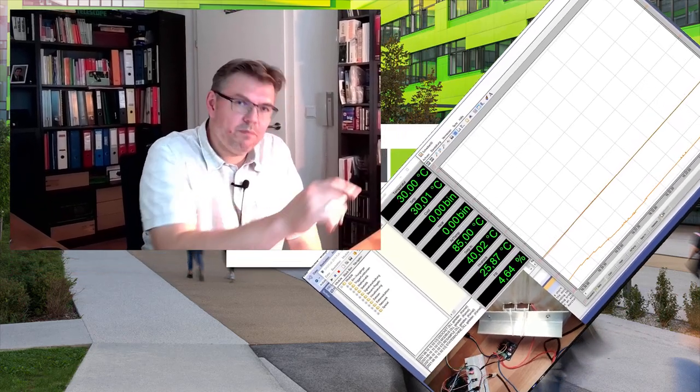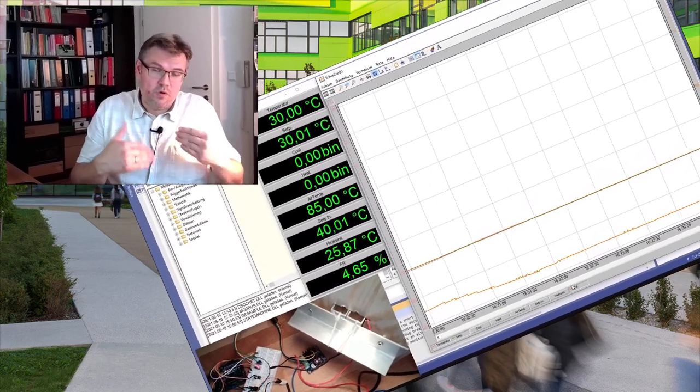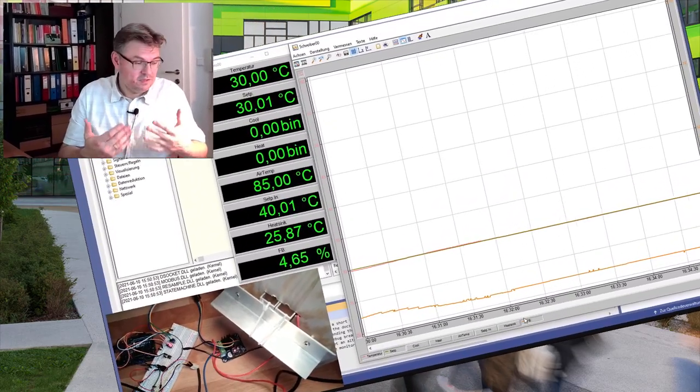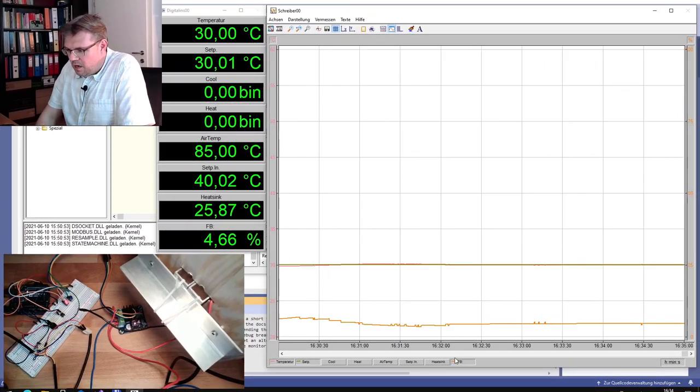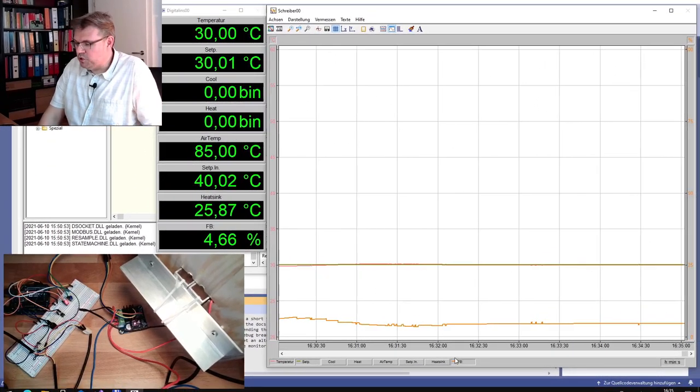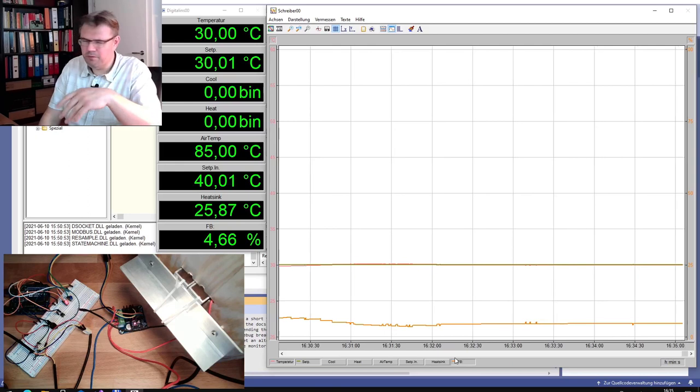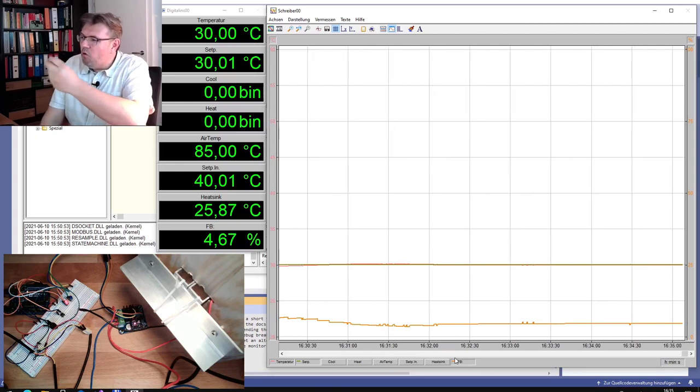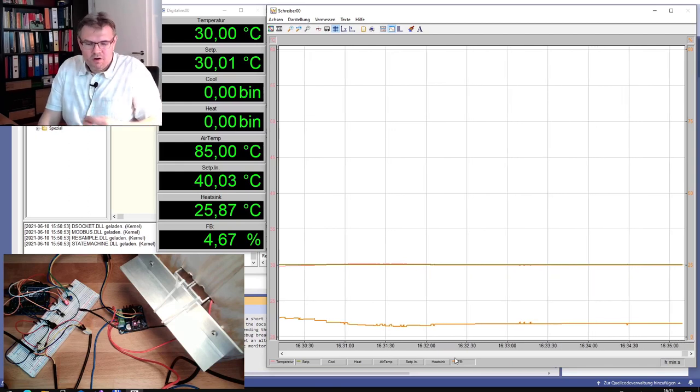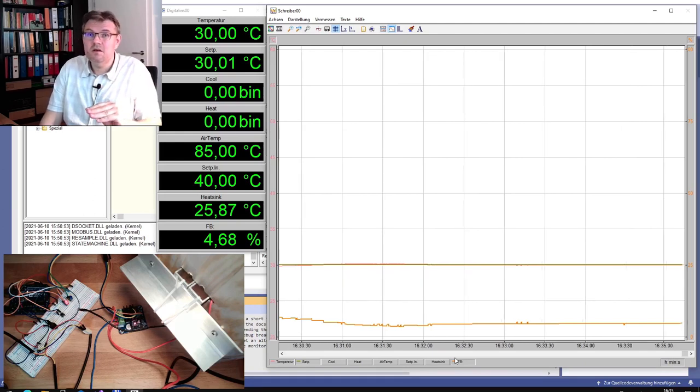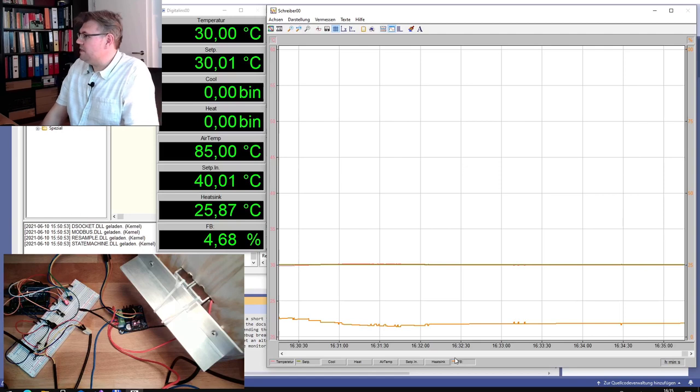Currently, it is adjusted to 30 degrees. And I will do then a push of the button, I will jump to 40 degrees. So I will do a reference value jump. This is what I am going to do. And we want to measure the rise time, we want to measure the overswing time, we want to measure the overswing width. Simply, all those quality or characteristics from the response we want to see.